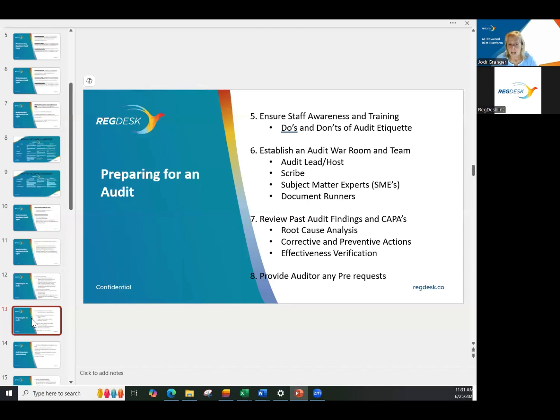Number 7 is looking at past audit findings and CAPAs. Every auditor will absolutely be looking at previous audit findings that they themselves have found or that are publicly available. If it's an FDA 483, they're going to be looking to see, have you really looked at a root cause analysis for each of those findings? Have you implemented appropriate corrective and preventive actions? And if you have implemented them, were they effective? So there's an effectiveness verification step that some companies miss. They think they've made all the corrections, but they've never checked to see if they've been effective. And so that's a key part of the process that an auditor will indeed look at.